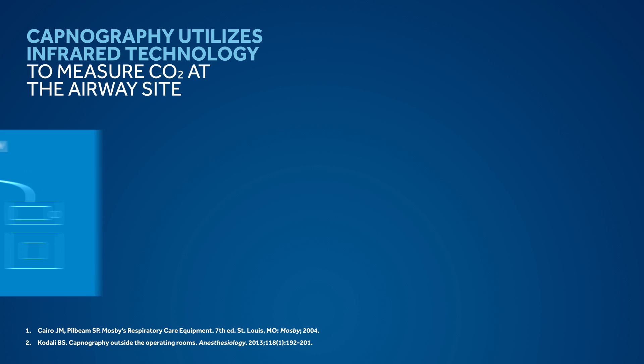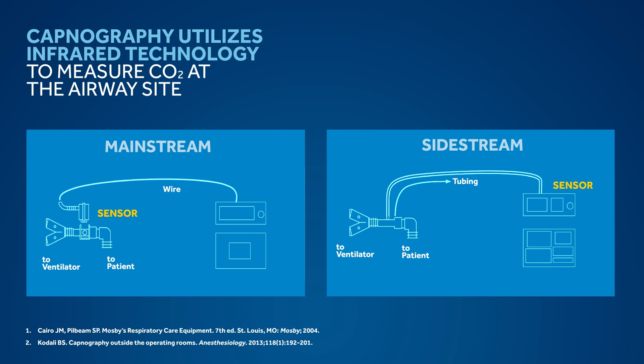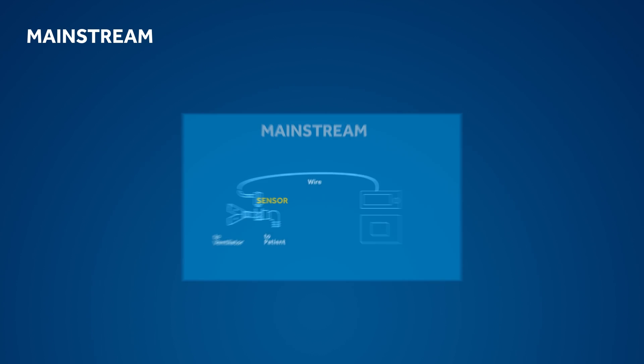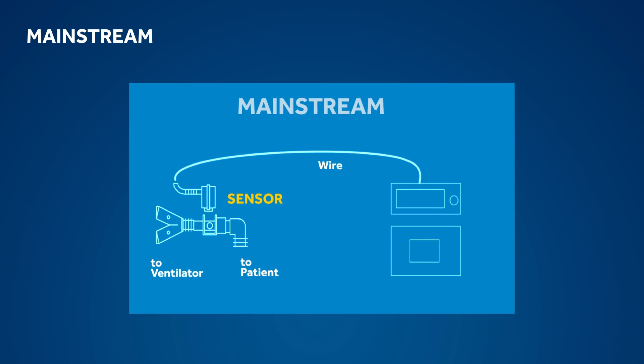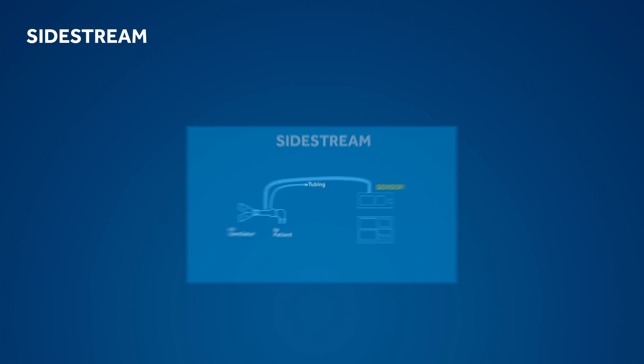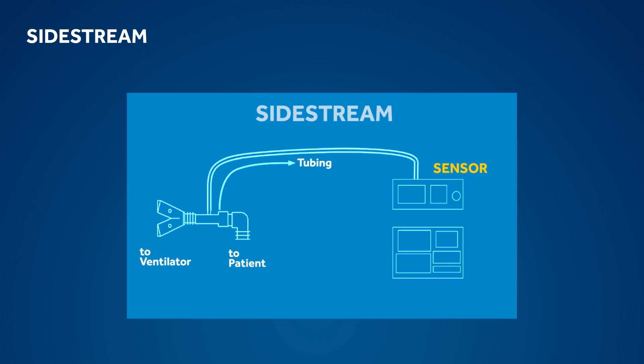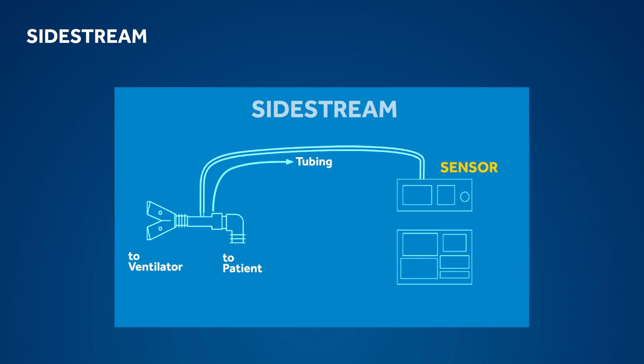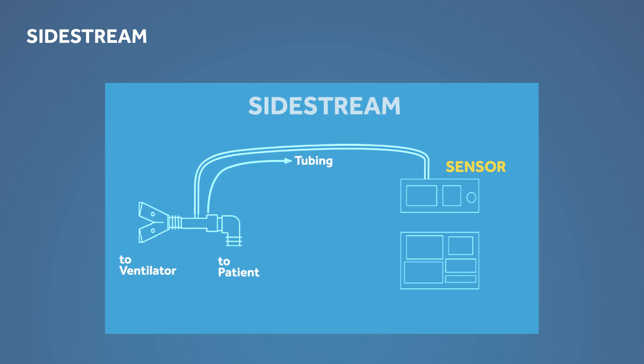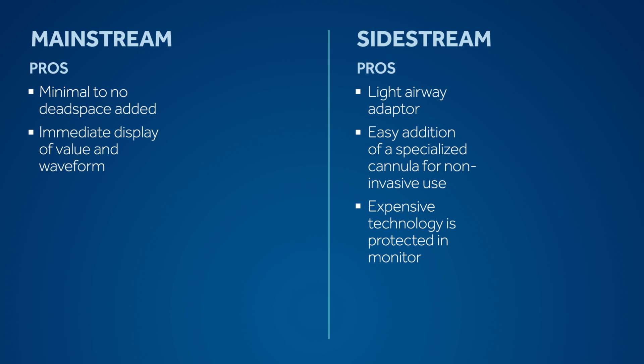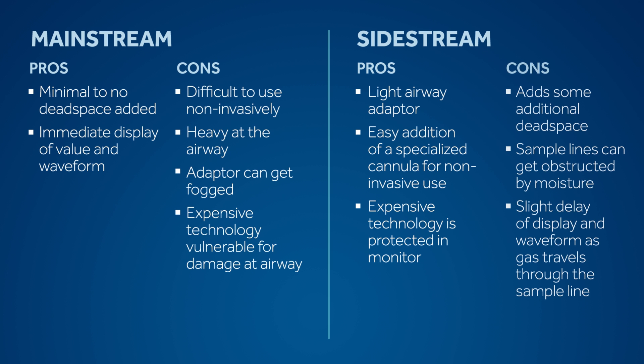There are two types of sensors that capnography uses to measure ETCO2: mainstream and sidestream. Both sensor types utilize infrared technology to measure CO2 at the airway site. The mainstream sensor is interposed between the tracheal tube and the breathing circuit. In sidestream sensor technology, the respiratory gases are diverted via an adapter and a sampling line to the monitor housing the infrared sensor. Traditional CO2 sensors and sampling lines, both mainstream and sidestream, have certain limitations that can contribute to inaccurate readings and restrict use within certain patient populations.